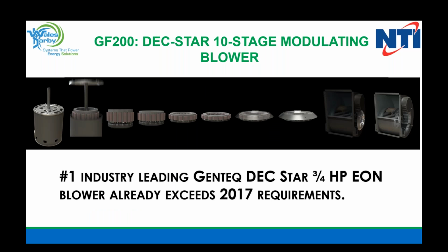This right here, this is a big deal. This is a DEC-Star blower. This is a 10-stage modulating blower. So we're used to seeing a motor and everything in a normal blower, and it usually is tucked in either the left or right side, which theoretically reduces the airflow for your return if you put it into the same side, as that big blower is blocking the wheel. So this is an industry-leading technology. It's DC technology. So basically what we do is we put this together, and the motor, really, the two pictures you see over there to the right of that, just before the two blowers, that's basically the motor.